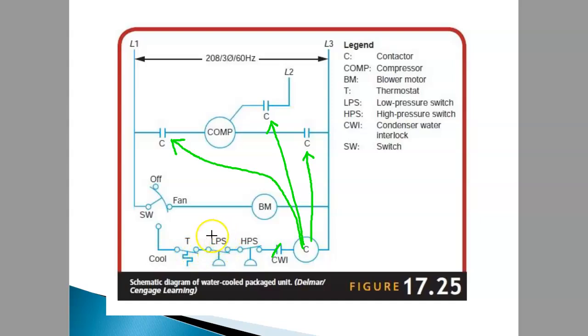And then we have at the same time the high pressure switch and low pressure switch has to achieve the desired pressure that we set. For example, this one is not too high, if the compressor or the system is too high pressure, then this one will be open. If the pressure is too low, this one will be open. So you need to have the pressure that we set. And then the thermostat is to measure the room temperature. So if it's higher than the setting, for example, we set 24 degree for the room, it achieves 26, then this thermostat will move from down to up in position and touch this point and make this line have the current, and will energize this relay and make the compressor running.